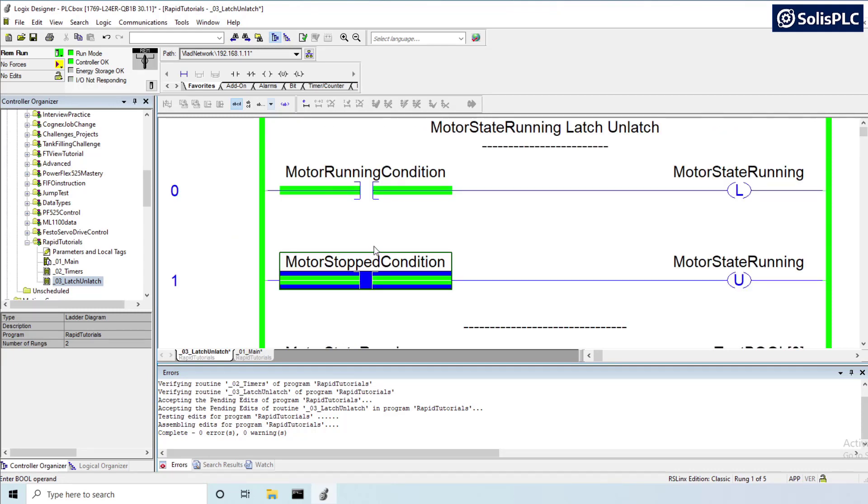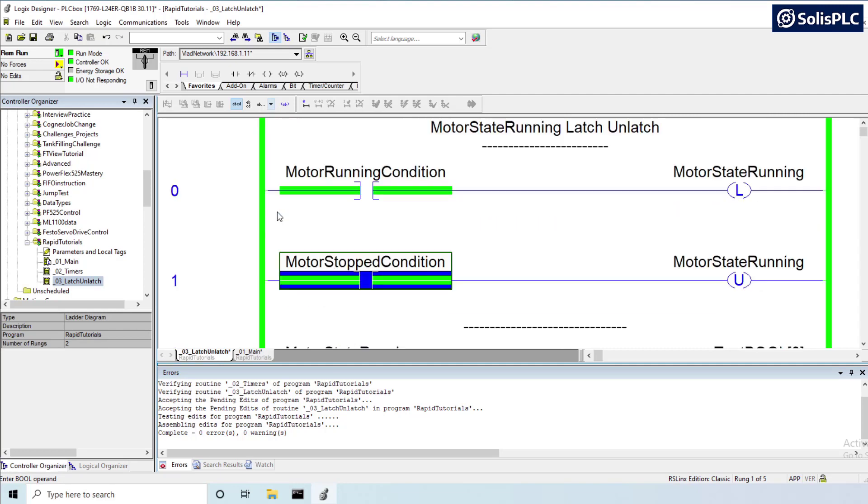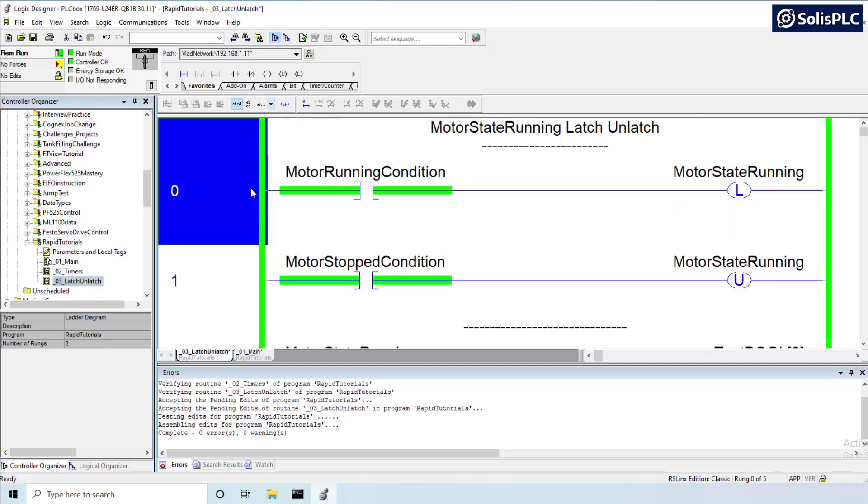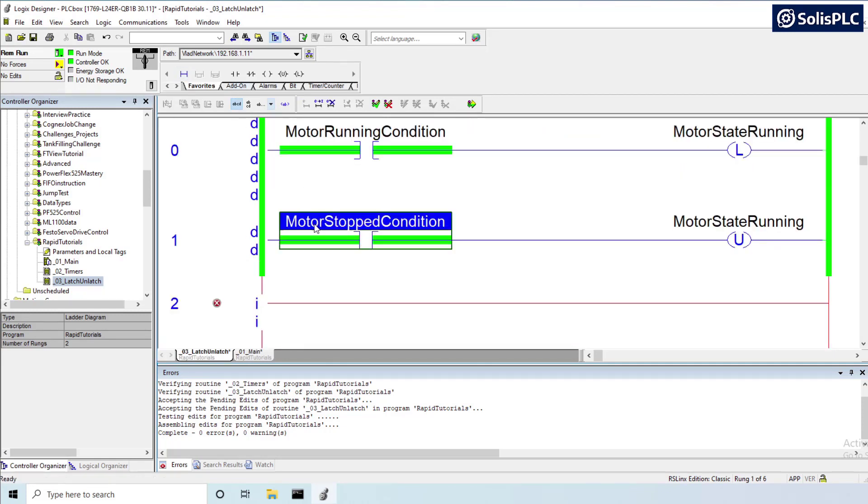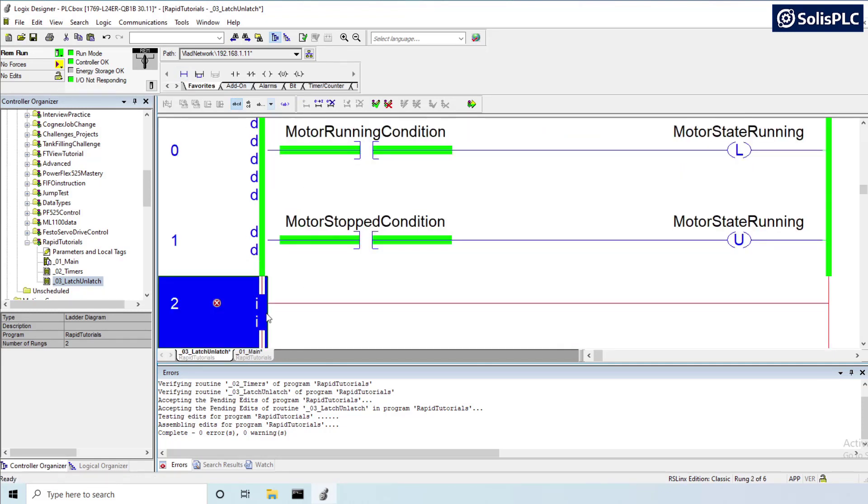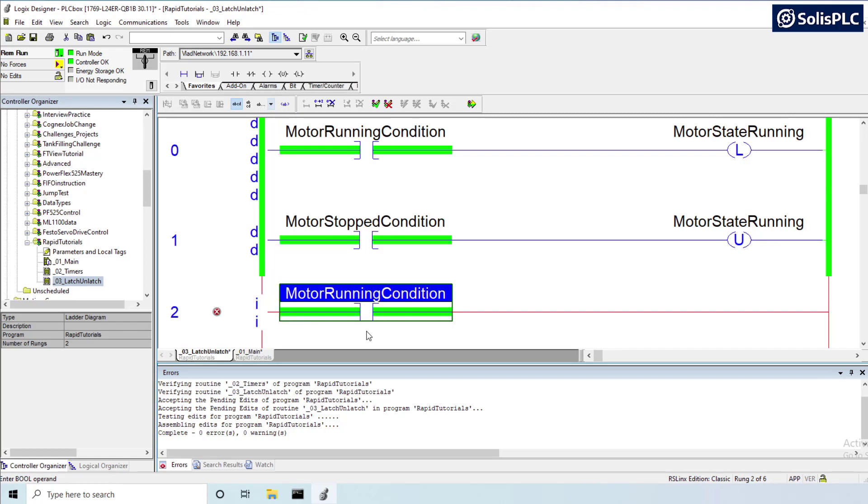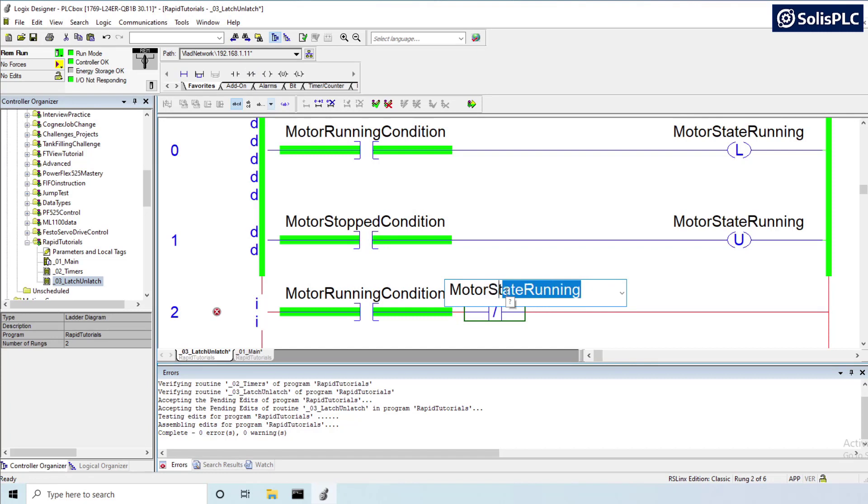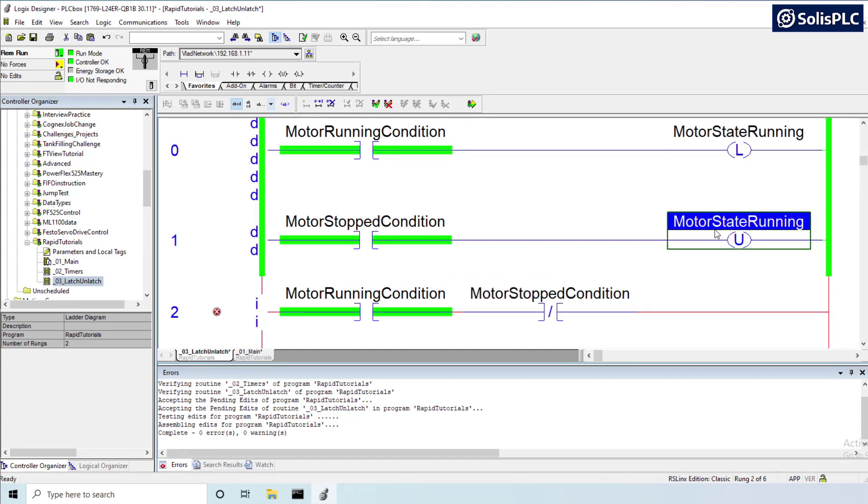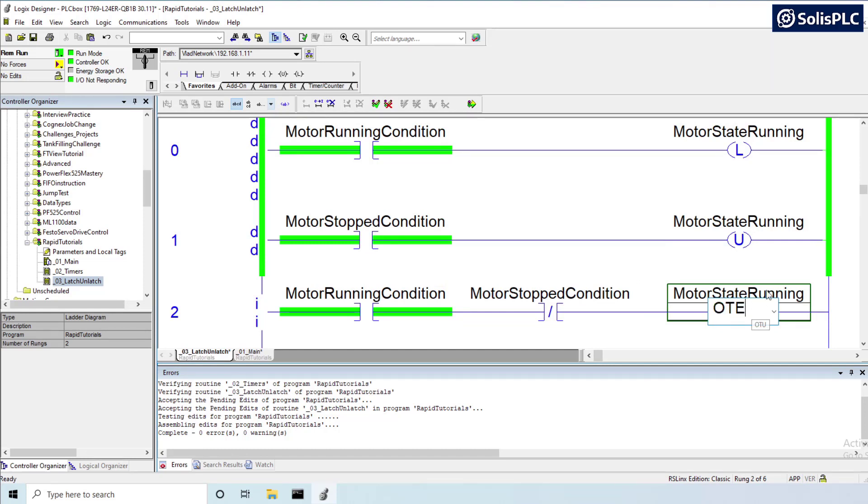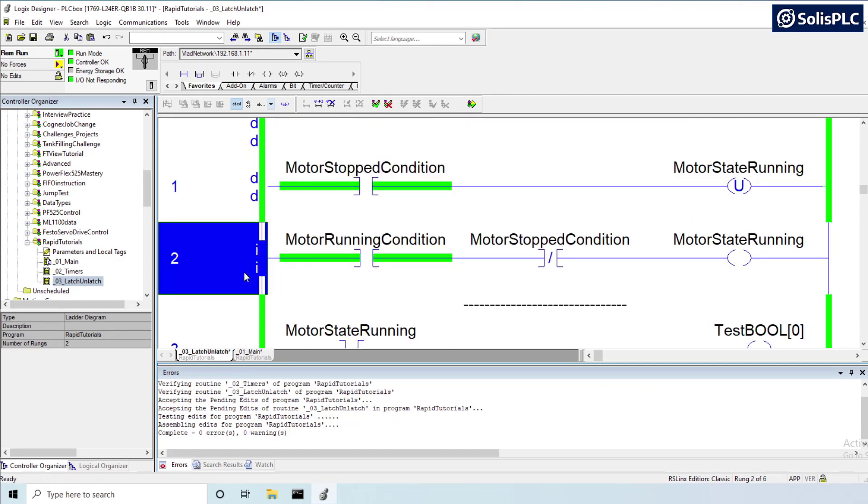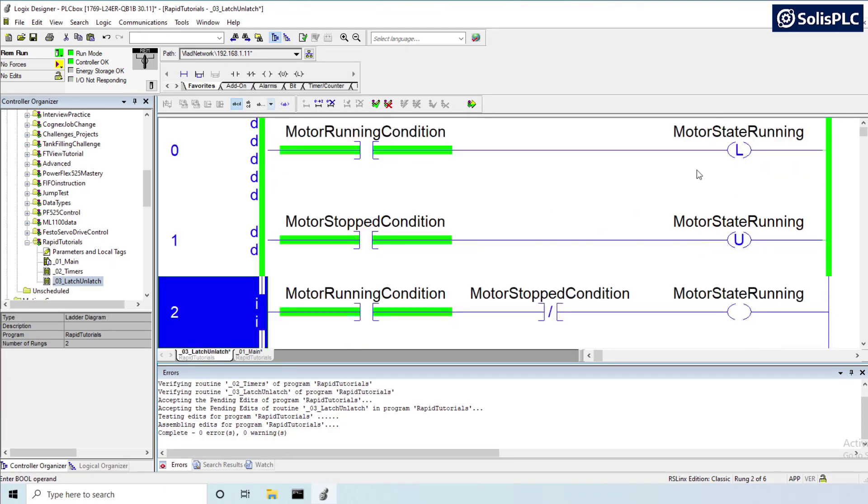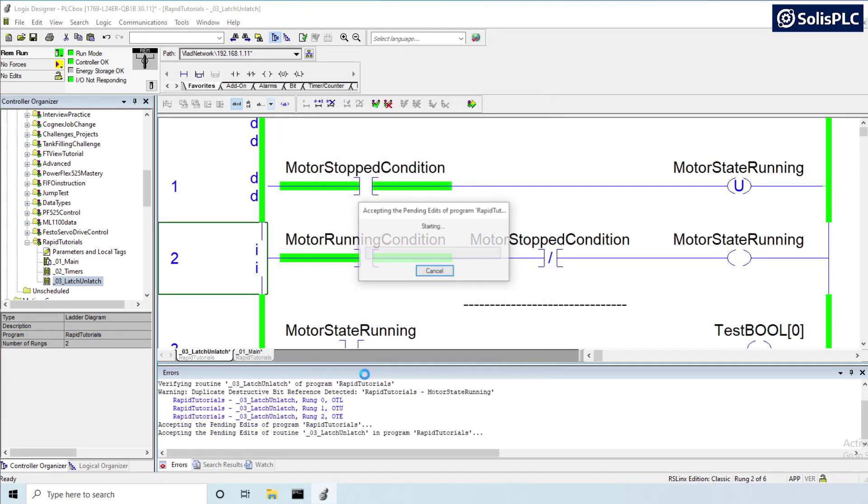Now once again in order to avoid this practice what you should be doing is instead of creating these two rungs, so I'm going to just delete them, I'm going to add a new rung and this is going to be motor running condition and here I'm going to use an XIO for the motor stopped condition, so motor stopped condition. And motor running is going to be an OTE because an OTE will take care of both states and it's not going to allow you to flip-flop the logic as you've seen here. So if I compile this...